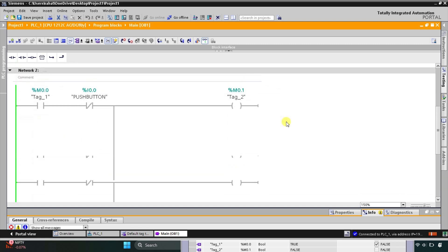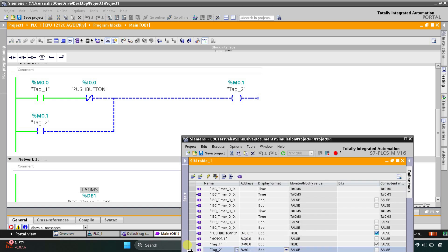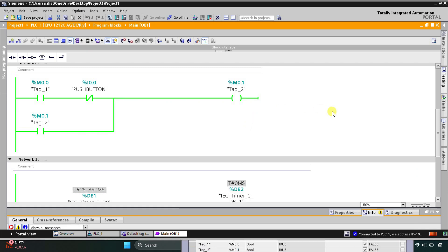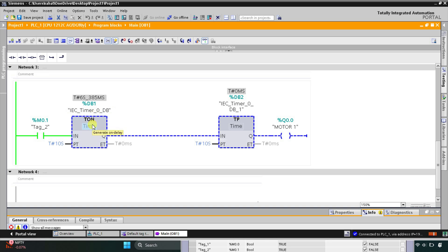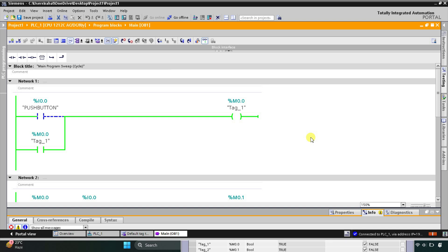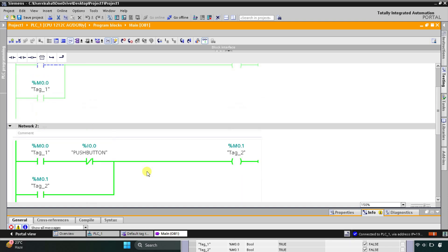When push button is pressed, M0.0 gets true. When I release it, M0.1 gets true and the timer starts — it will wait for 10 seconds, and after 10 seconds Motor 1 turns on. It will remain on for only 10 seconds: 5, 6, 7, 8, 9, 10 — and after that Motor 1 gets off. So when push button is pressed and released, this timer starts. That was all about this example — thank you for watching.